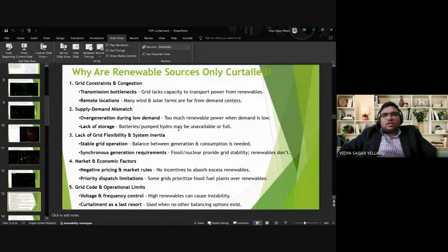So in the case of these constraints, as explained in the previous slide, the renewable sources are curtailed when there are constraints. That means when there are overloads in the network. Renewable energy sources are curtailed because many wind and solar farms are situated far from the demand centers, and since those are far, there might be weak network conditions or less short circuit power. Because of that, the grid lacks capacity to transport power from renewables, and there is a supply-demand mismatch, with power generation during low demand.